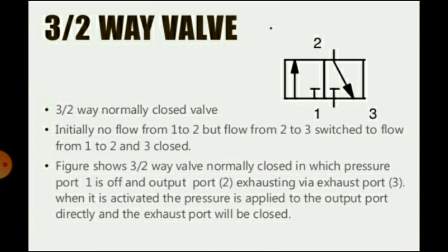Then the 3 by 2 way valve. The symbolic representation is given in this slide for the 3 by 2 DC control valve. So the 3 by 2 way valve is a normally closed valve. Initially there is no flow from 1 to 2, but there is flow from 2 to 3. Switched, there is flow from 1 to 2 and 3 is closed.